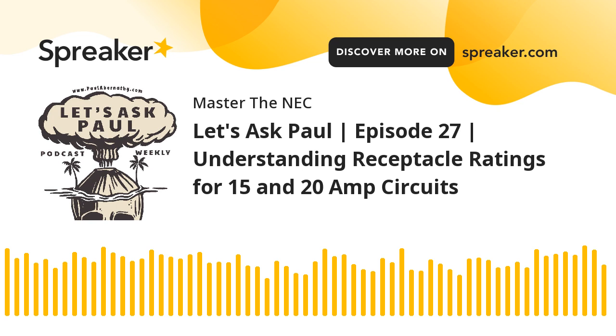So in today's episode of Ask Paul, we get asked, Paul, can you explain the ampere rating of 15 and 20 amp receptacles, as well as single receptacles on an individual branch circuit when it's 15 or 20 amp rated? Okay. Now, first thing I'll tell you is that it goes all the way up to 50 amps, and you would really want to go look at 210.21, B1, B2, and B3, and you'll see a little table associated, and it kind of gives you an idea of the ratings of receptacles based on the branch circuit. And it should be pretty straightforward. But again, there are a few things associated with it that do get people confused. So we're going to go over those today and kind of hash those out. And maybe that's the question that the individual is asking. Hopefully I nail it. And if not, reach out to me again and ask for more clarity, and I'll be more than happy to do that.